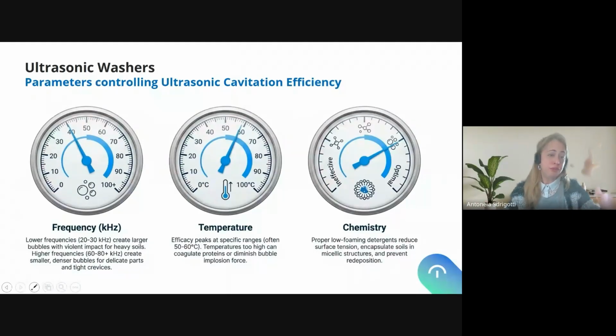Right? The first parameter that I have introduced before, and is one of the most important ones, is the frequency, the working frequency. And this will be delivered by the transducers. Okay, so this is the main job of the transducers. And this is very important because inside an ultrasonic washer, we will definitely need every transducer to be working correctly.